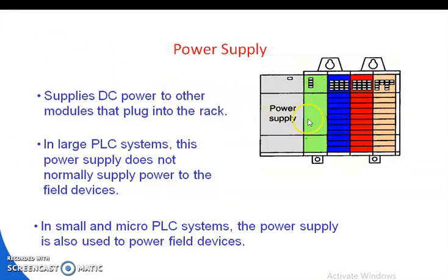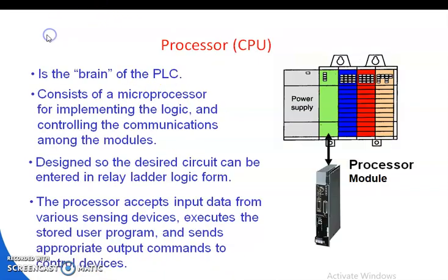Next, power supplies. The power supply supplies DC power to other modules that plug into the rack. In large PLC systems, this power supply does not normally supply power to the field devices. In small and micro PLC systems, the power supply is also used to power field devices.